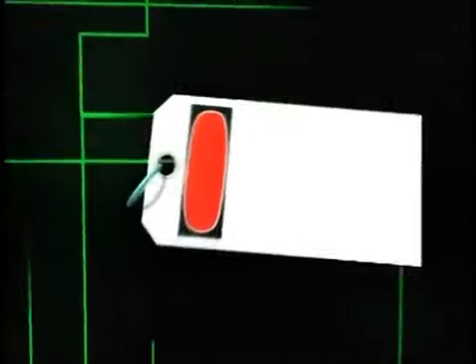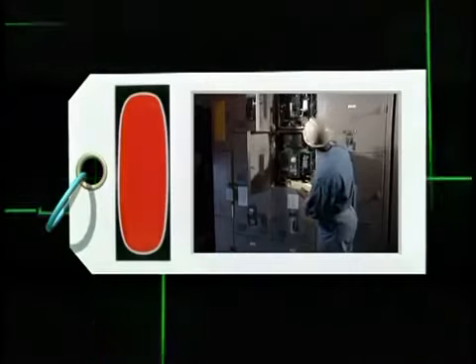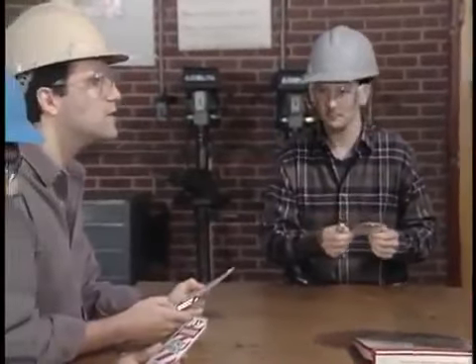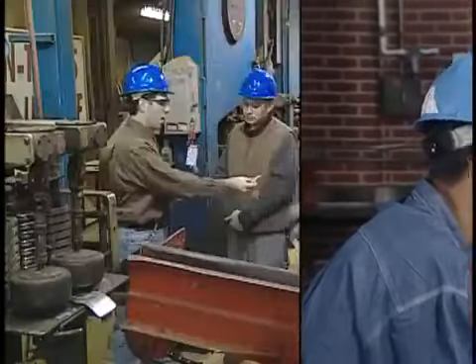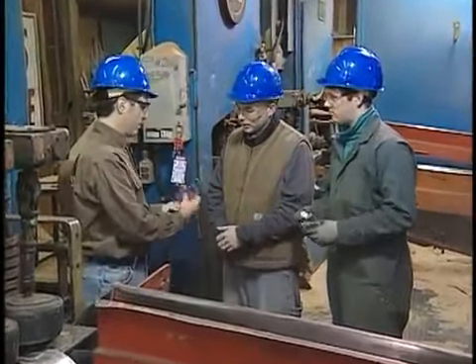If only tags are used, extra steps must be taken to prevent the energizing of machinery, such as removing a valve handle or blocking a controlling switch. Employees should be trained in the limitations of the tagout system. It's very important to obey the warnings on tags, especially since they will not physically keep you from turning power on. Your employer will provide all lockout/tagout materials needed.